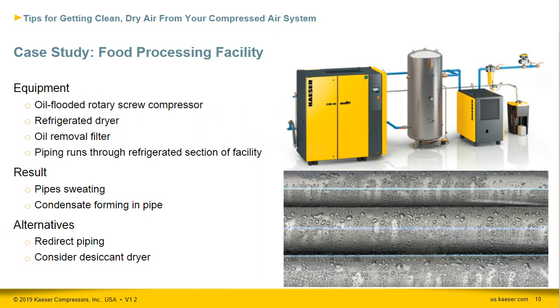However, the end user continued to get moisture downstream in a certain area. Nothing seemed amiss about this particular area or really in the compressor room, but when we traced the piping between those two points, that piping ran through a refrigerated section of the facility and then back out. So the forecast would always call for rain inside and outside of the pipe because there was additional cooling of the air because of the refrigeration section. That condensation wasn't planned for and it wasn't removed.